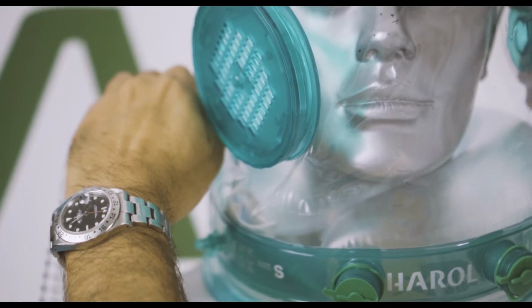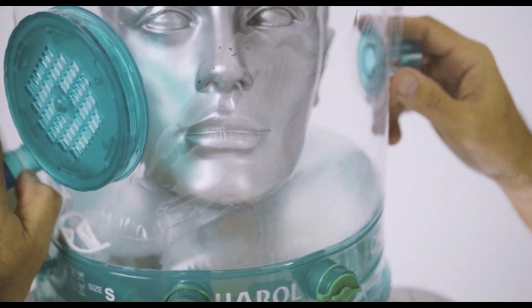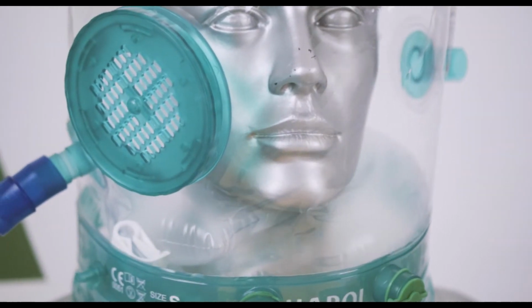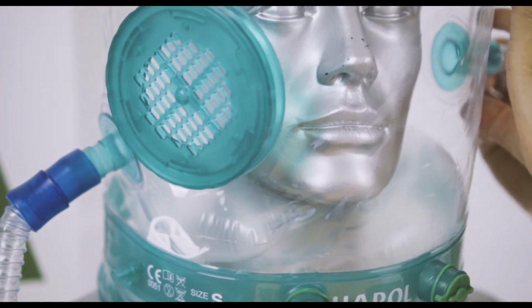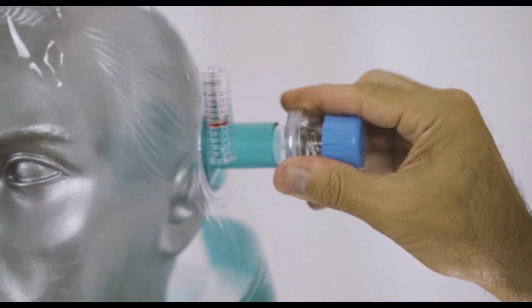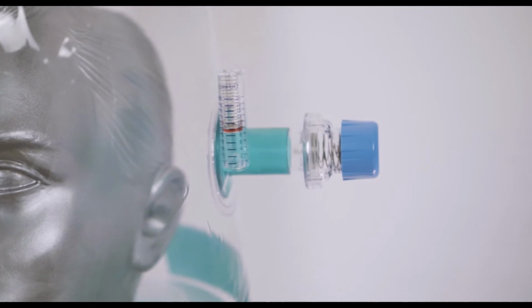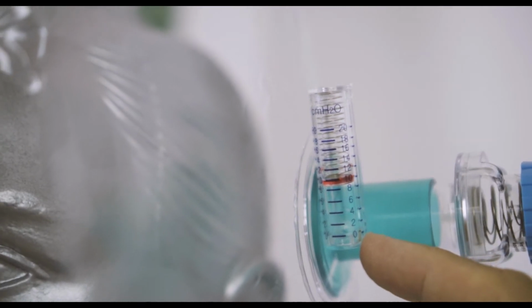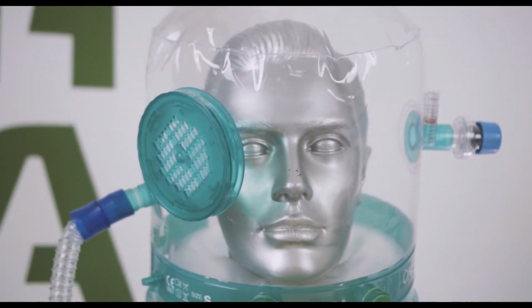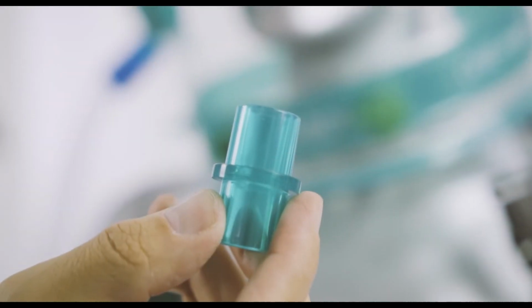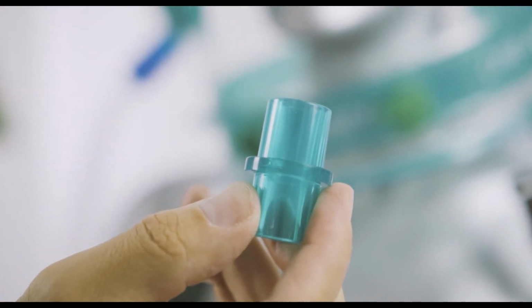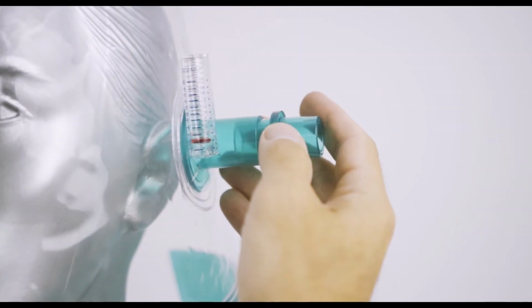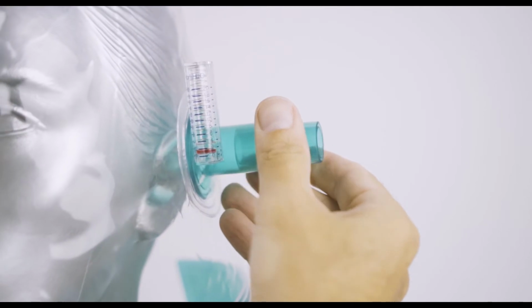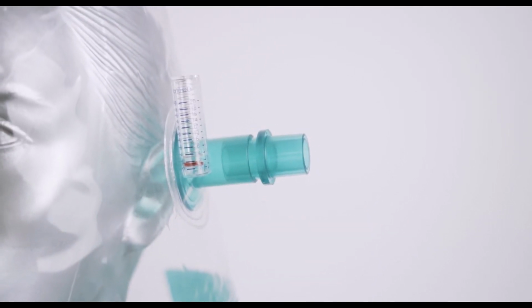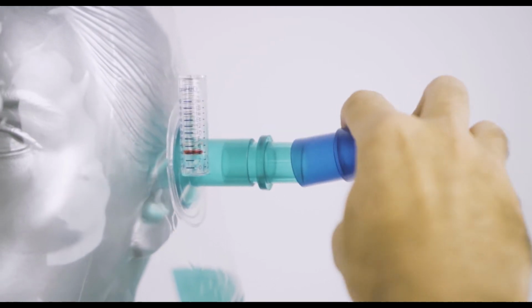On the sides of the tent there are two connections, a 22mm male inlet, conforming to ISO standards, used for connecting the tube that will provide the flow, and a 22mm female outlet, also conforming to ISO standards, on which the PEP valve will be connected. Next to the outlet connection, you will find an integrated manometer for PEP measurement. With the helmet, a male-to-male adapter is provided to connect the outlet with an external ventilator, for use in a dual-tube CPAP therapy. Regardless, by international guidelines, it is preferred to execute the CPAP therapy with a high-flow generator and a PEP valve, instead of a ventilator.